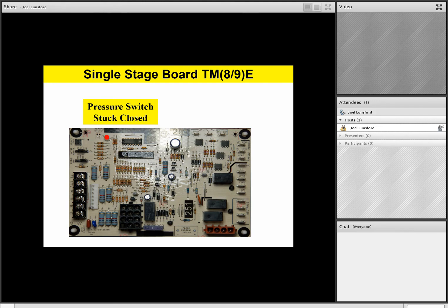However, during diagnostics, sometimes technicians will jumper a switch to try to test it. And possibly, they'll try to rewire something, so double check that wiring to make sure the wiring hasn't been altered, or that the technician that was there ahead of you has not rewired something. So double check that wiring, because sometimes technicians use jumpers, and sometimes they'll try to wire around something to bypass it.